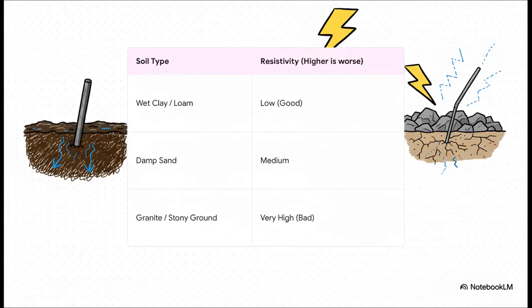This brings up a crucial point: not all ground is created equal. The standard has data on something called soil resistivity. Wet clay is a fantastic conductor with low resistance, but dry, stony ground or solid granite is terrible. So engineers have to know the local geology to design an earthing system that's actually going to work. Sometimes they have to drive those electrodes way deeper just to find soil that's good enough.